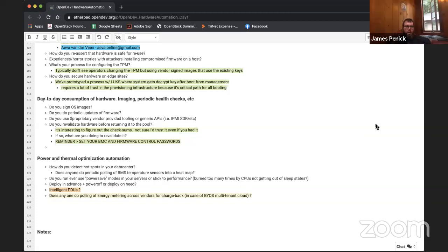Yeah. We actually build our newer data centers that way now. If you look up the Verizon Media or Yahoo Compute Coop data centers, this is all public information, there are some really cool infographics that'll do a better job explaining this than I can, but they're really interesting because they're built around the idea of passive cooling. So the whole data center is built sort of like a gigantic chicken coop. It looks like a really big barn, basically. And so there are louvers on the outside of the buildings that air comes in through.